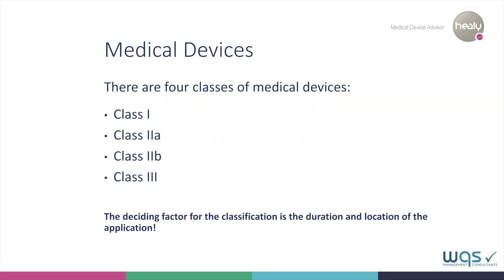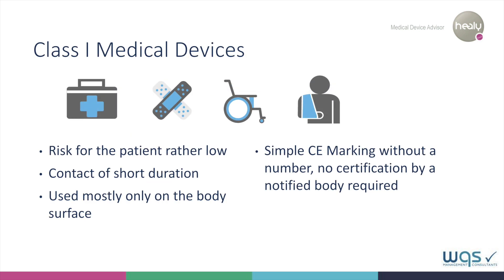There are four categories of medical devices: Class 1, Class 2A, Class 2B, and Class 3. They are classified according to the duration of the application and where in or on the body they are applied. An adhesive plaster is a good example of a Class 1 device — applied to the body surface for a short period of time, resulting in a lower risk for the user. The same applies to bandages or a wheelchair. These products carry a simple CE mark without a number, and are therefore not certified by the notified body.